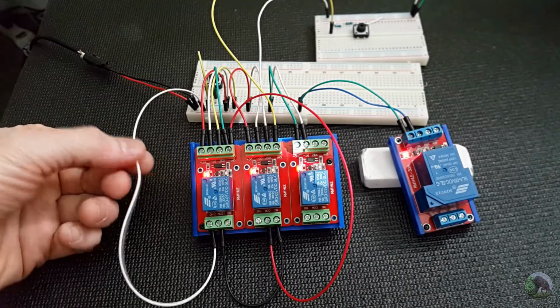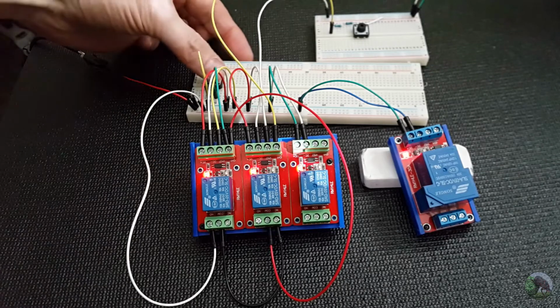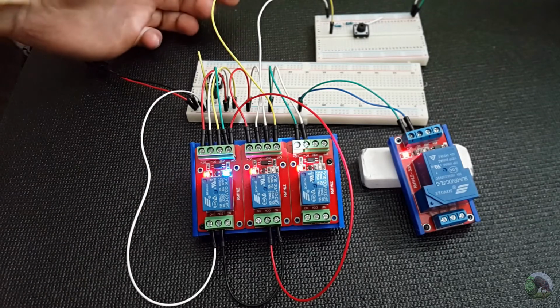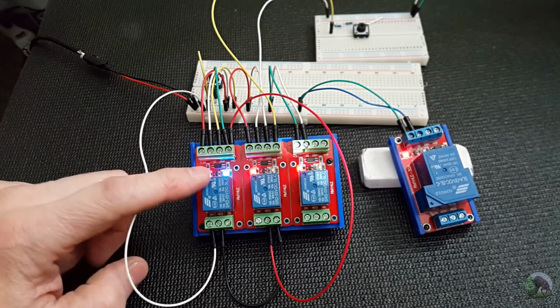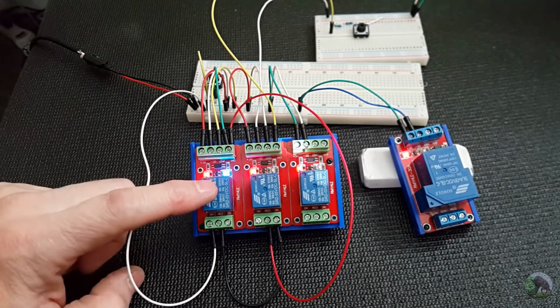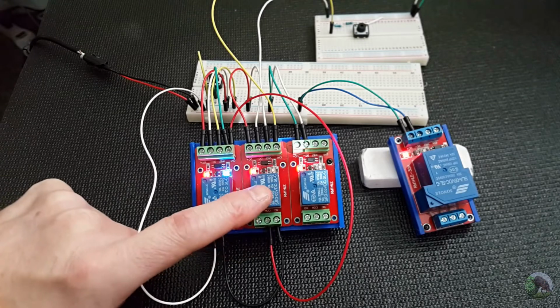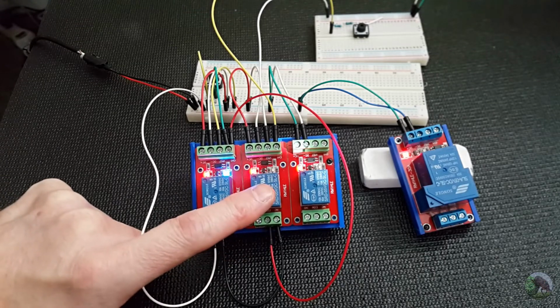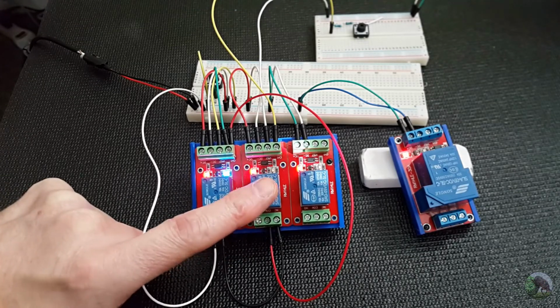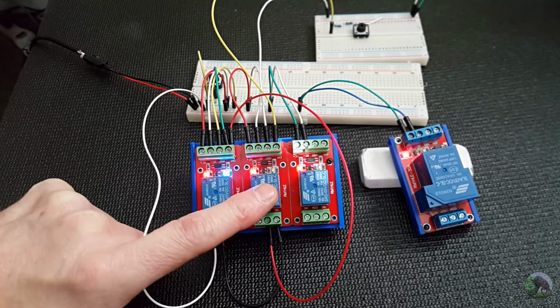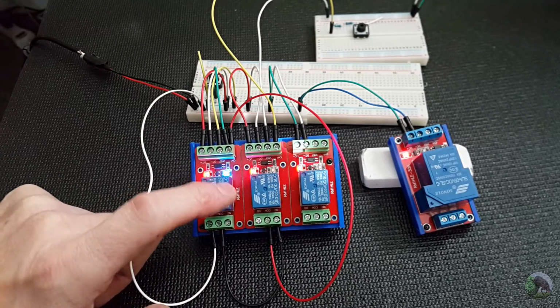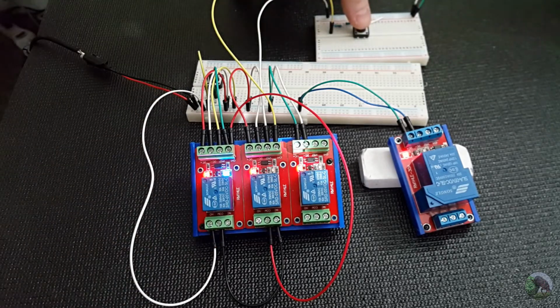So I've added three wires and changed the behavior of this system. Now when I press the button, the first relay comes on, but when I let go of the button, it actually stays on. So this relay is now latched, and its power is being passed through the normally closed contact of this relay. And so if we change the state of this relay, the power to this relay will go off.